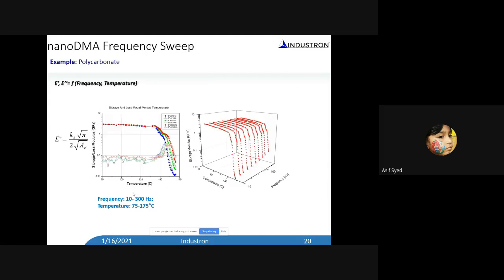Okay, I'm going to show a few examples here. This is a polycarbonate, and I mentioned the dynamic measuring capability: you apply a sinusoidal force and measure the sinusoidal displacement response and measure the stiffness, the storage component as well as the loss component. From the stiffness, you calculate the storage modulus and loss modulus. That is what is plotted here as a function of temperature. You can see the storage modulus drop at the glass transition temperature, and also the loss modulus shows a peak at the glass transition temperature. You can do that as a function of temperature as well as a function of frequency.